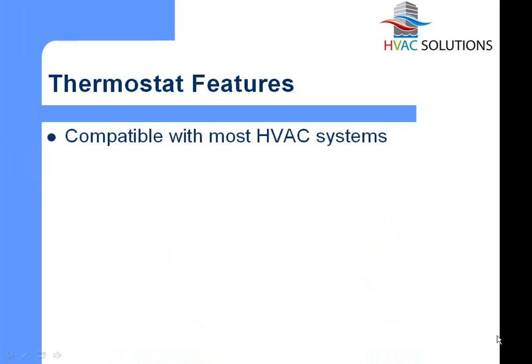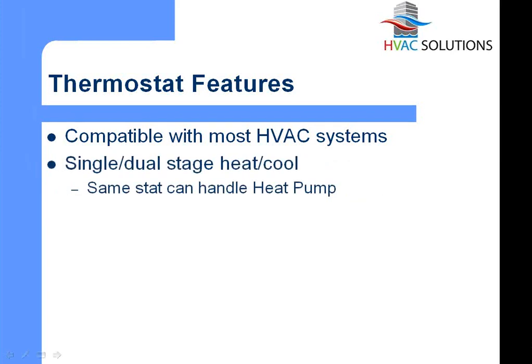We say that these thermostats are compatible with most HVAC systems, and most means 24 volts. So anything you can put a 24 volt stat on, like a furnace or a rooftop or anything like that, you can put a Proliphix thermostat on. From the thermostat standpoint, it wires exactly the same as a regular thermostat. It does require a common wire, like most higher-end digital thermostats require, so it can power up the display of the stat itself. So if you used to have an old 4-wire stat for one-stage heat and one-stage cooling, you might need to have a 5-wire scenario now for these thermostats. Although we do have add-a-wire kits to help you get around that if you can't pull new wiring.